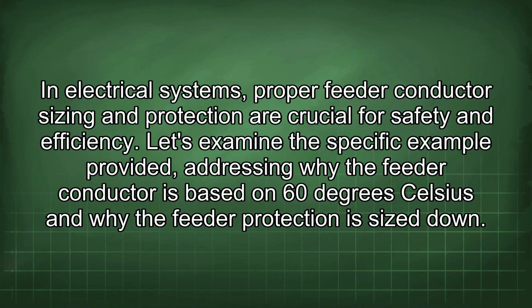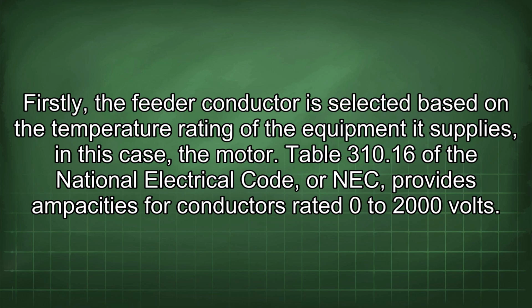In electrical systems, proper feeder conductor sizing and protection are crucial for safety and efficiency. Let's examine the specific example provided, addressing why a feeder conductor is based on 60 degrees Celsius and why the feeder protection is sized down. Firstly, the feeder conductor is selected based on the temperature rating of the equipment it supplies, in this case, the motor. Table 310.16 of the National Electrical Code, or NEC, provides ampacities for conductors rated 0 to 2000 volts.